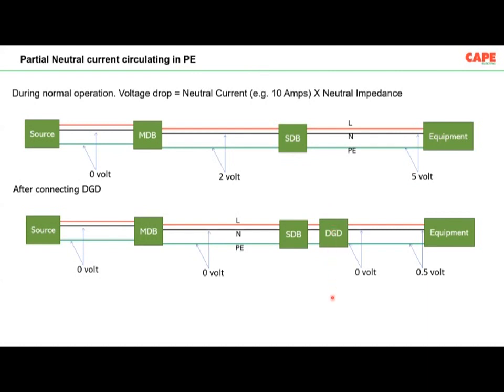As a result, you must understand the reason for this 5 volt. This 5 volt is due to the neutral current flow. The current flowing through the neutral conductor multiplied by its resistance will give you this voltage drop. Now, by making a shorting at this particular place, what is going to happen is, the neutral current will come up to this place. Then partial neutral current will flow through the neutral conductor and the balance current will flow through the earth conductor. This neutral current which is flowing through the earth conductor is a kind of circulating current.